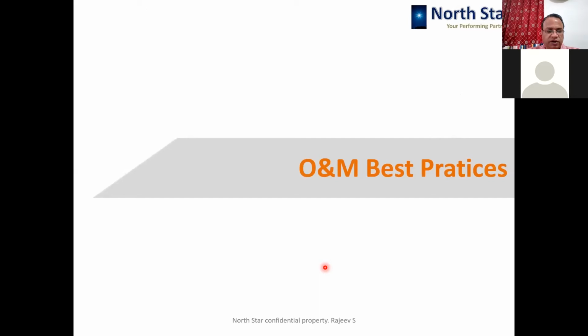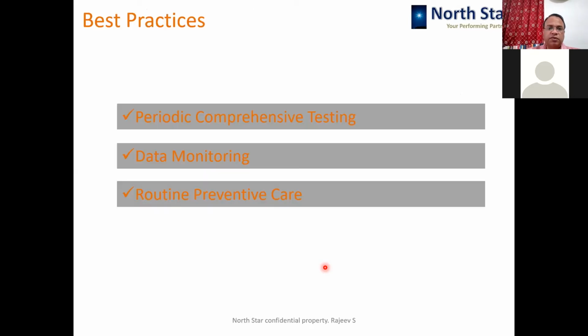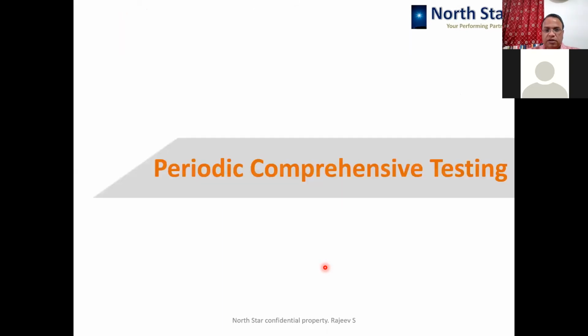Now, other than this, what else can be done as far as the transformer maintenance is concerned? So we have put 3 points over here. One is the periodic comprehensive testing, data monitoring, and routine preventive care. Periodic comprehensive testing, normally we do various tests as part of our routine maintenance activities, like we do insulation resistance, we do oil tests like oil BDV, oil PPM.